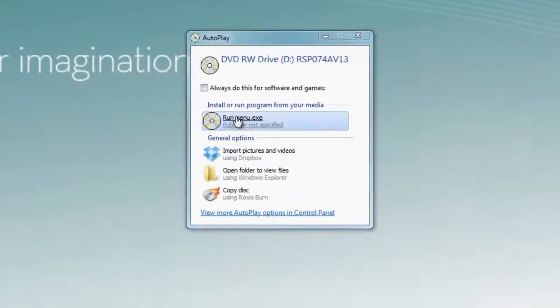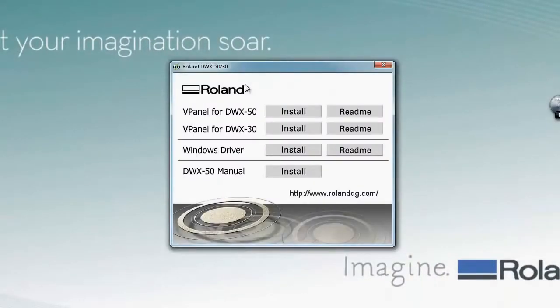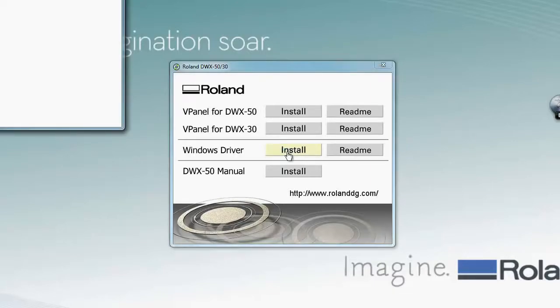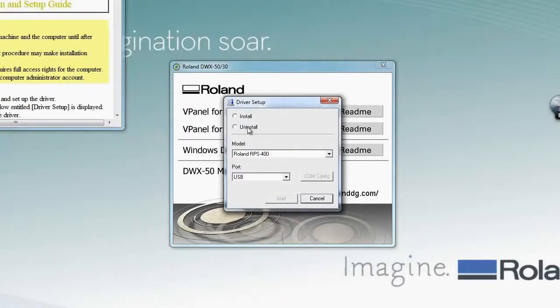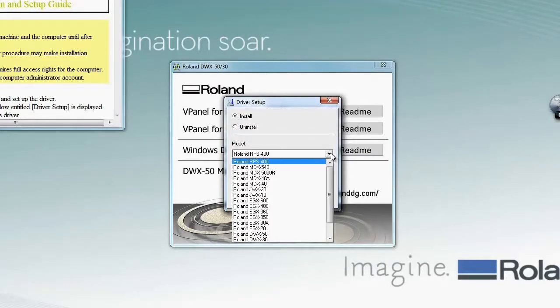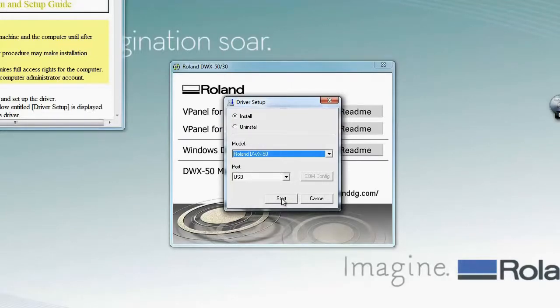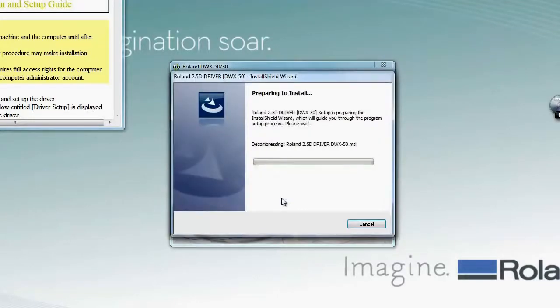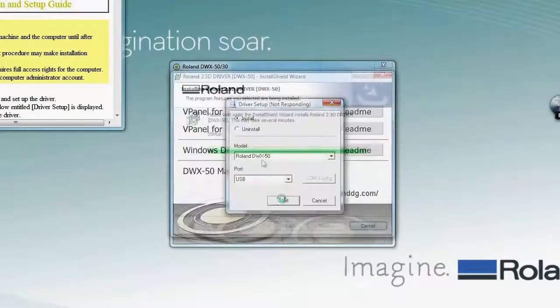Using the software CD that comes with your machine, run the software package and install your Windows driver first. Do this by clicking on the Install button and clicking the Install option on the driver setup. In the model, be sure you choose the DWX-50 machine in the drop-down, and you will be connecting this through a USB port, so make sure your port is USB before you hit Start to follow the wizard through the setup process. At this time, the unit should be powered off and the USB cable should not be plugged in.